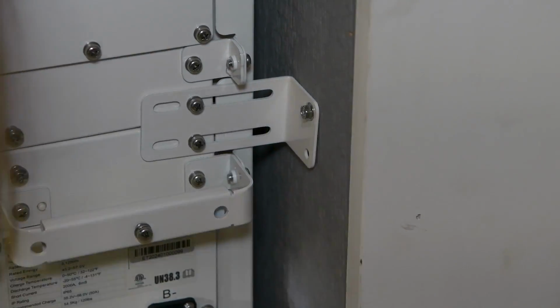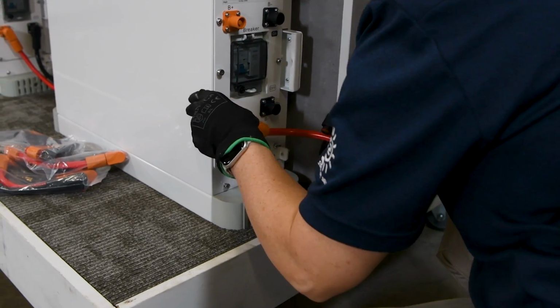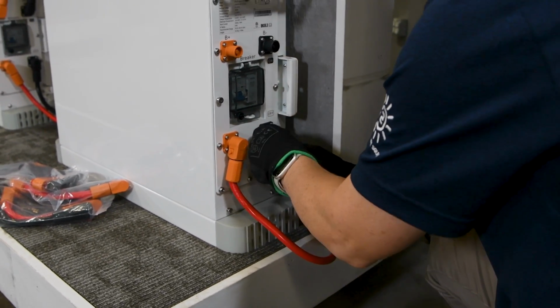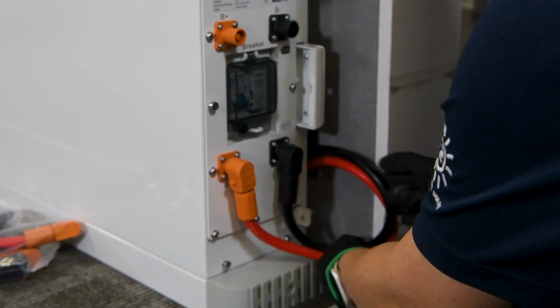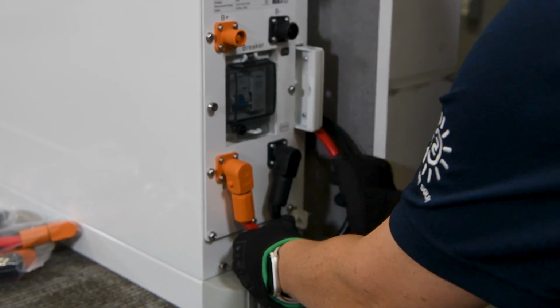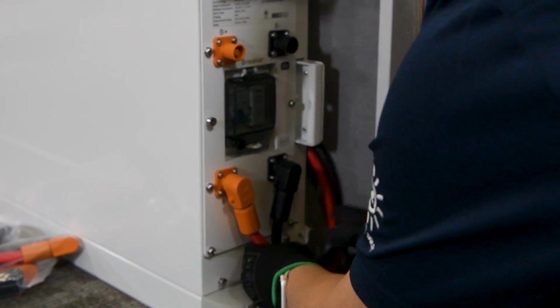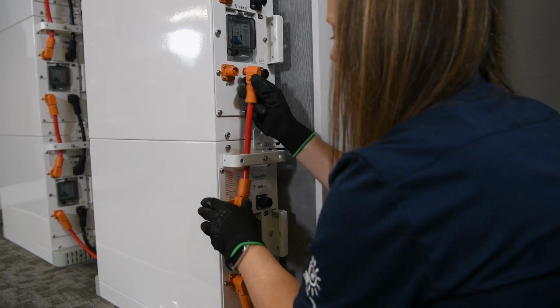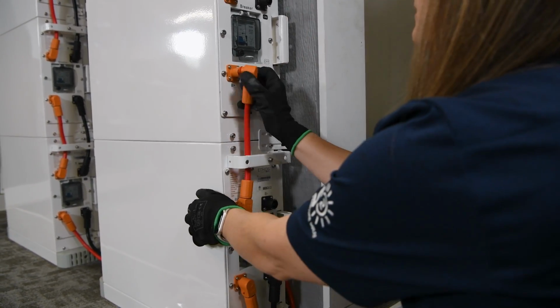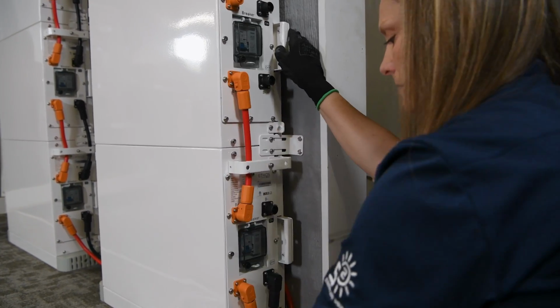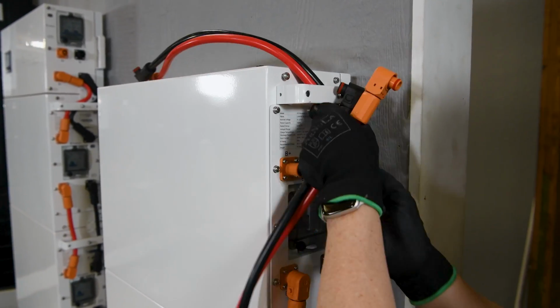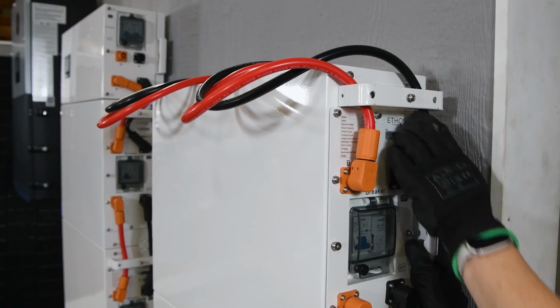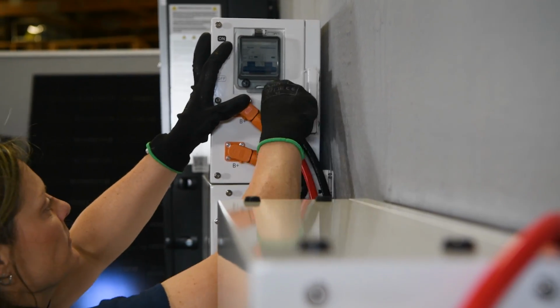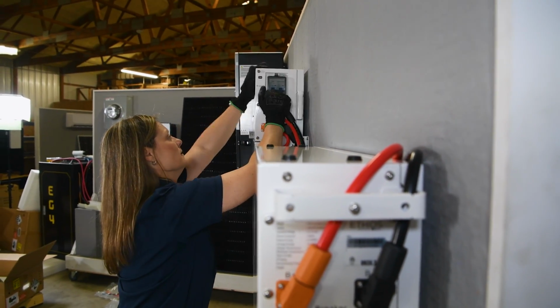Now notice, rather than extending the cables from the bottom to the top within a single stack, we'll connect them from the bottom battery terminals of our first stack directly to the bottom battery terminals of our next stack, ensuring red cables are attached to positive terminals and black cables to negative ones. We'll mirror the daisy chain connections up the stack just as we did with the first, using our battery cables. Upon reaching the top, we'll extend the cables from the top terminals of the second stack back to the top terminals of the first stack, thus completing our parallel circuit configuration.